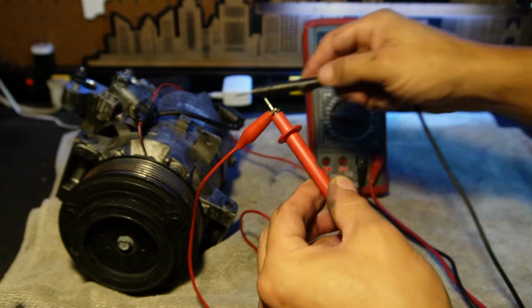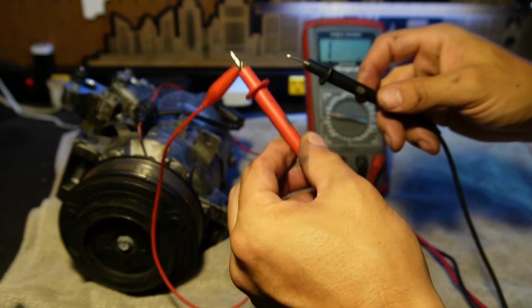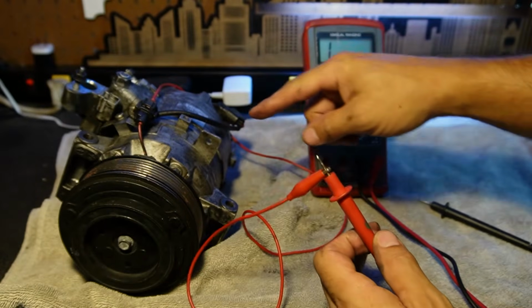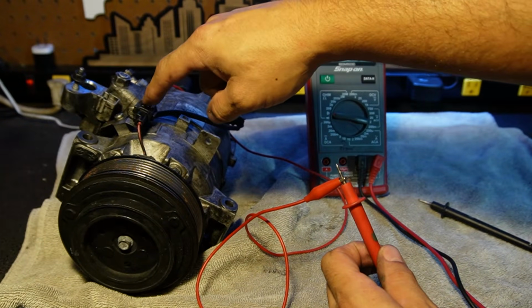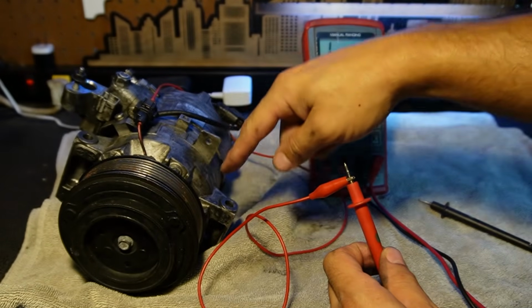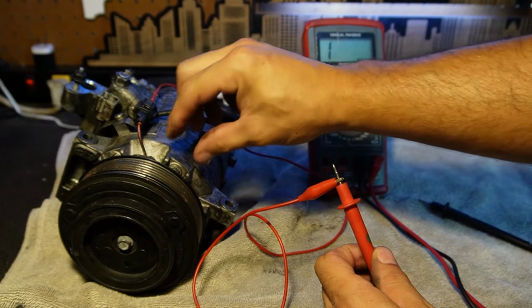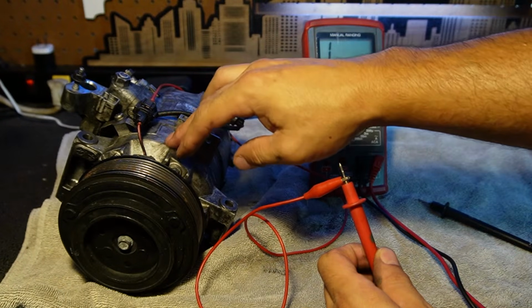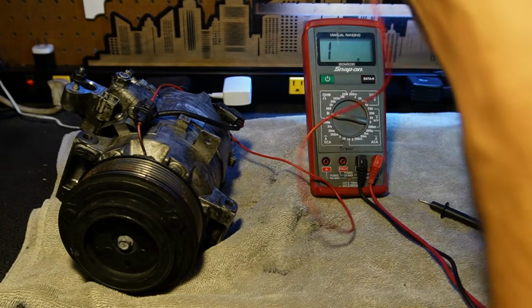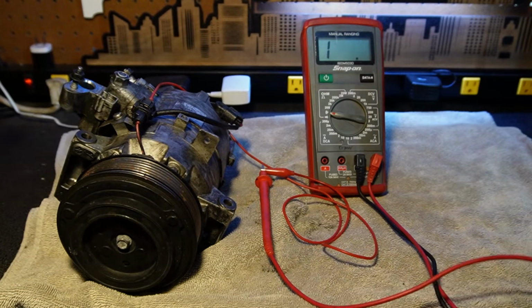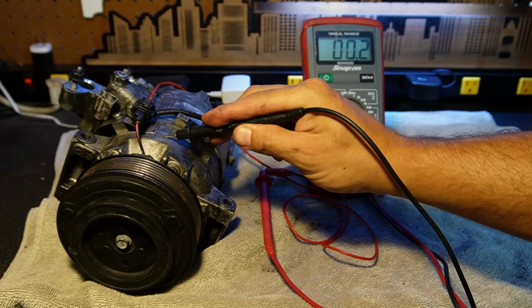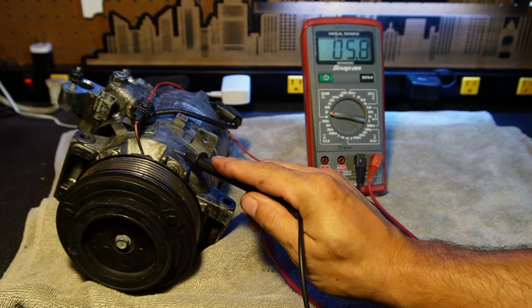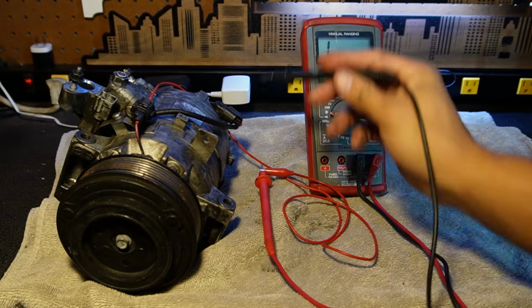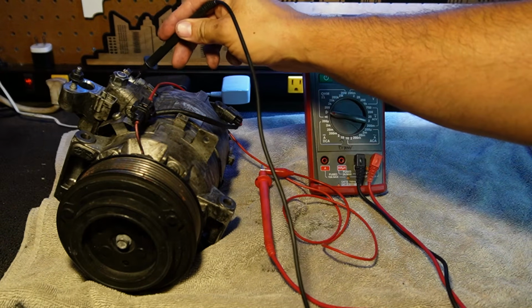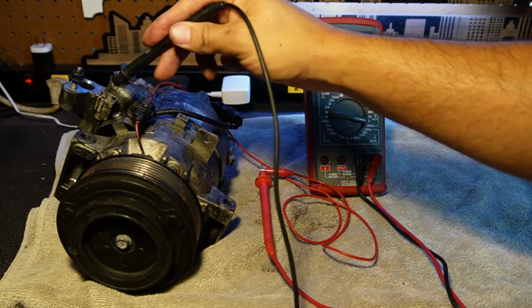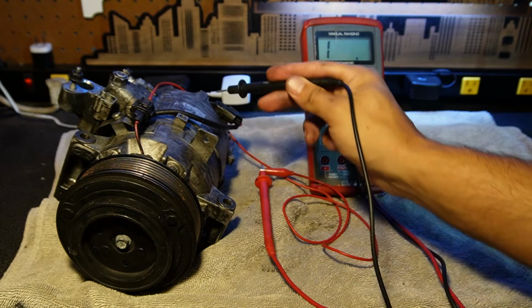That means there's a connection from here to here. So now what we're going to check is if there's a connection from this wire through the coil into the case, because the case is the ground on this compressor. I'm going to set this to the side and simply touch the case, and you can see the multimeter is moving. You could touch it anywhere on the case, it's all ground.